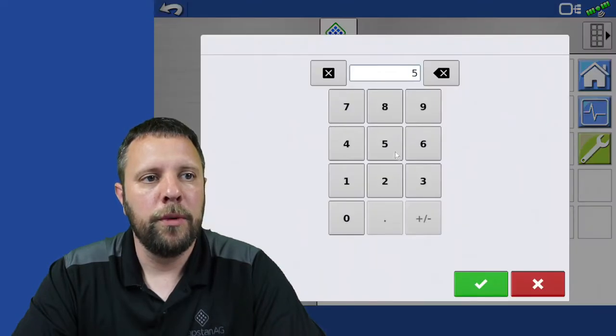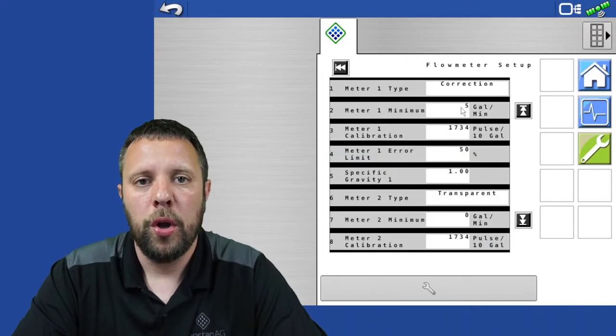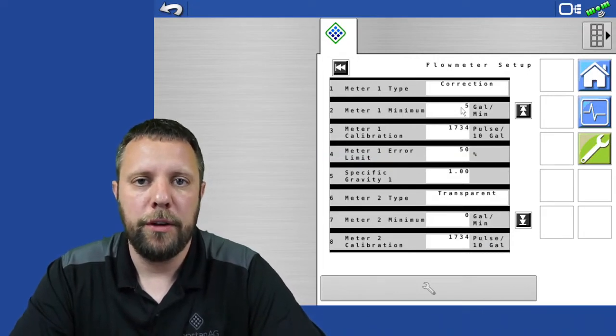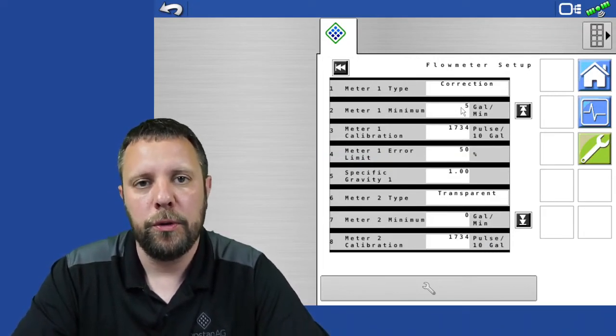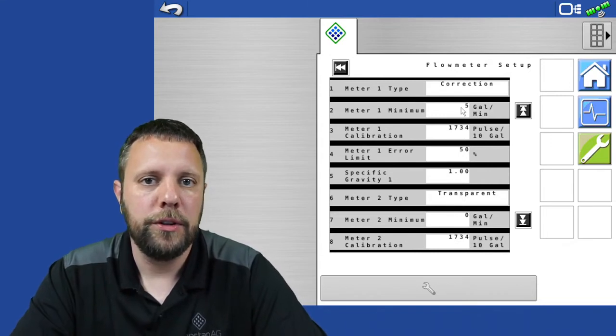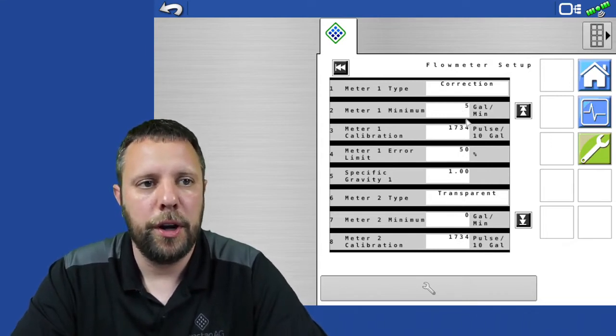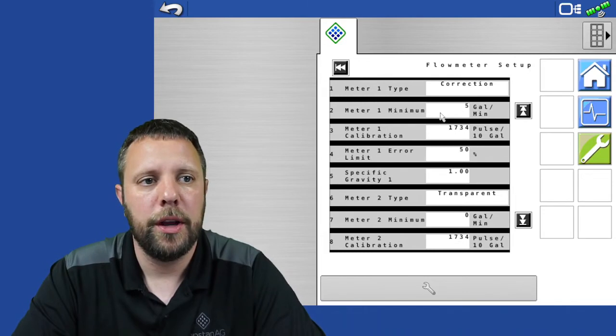Meter 1 minimum we usually set to 5 gallons per minute. Whenever the flow is less than 5 gallons per minute through the flow meter, we'll use the pressure sensor and the duty cycle and speed to calculate the flow rate, which is more accurate than the flow meter at that point.